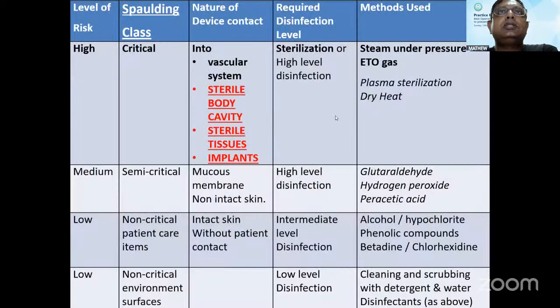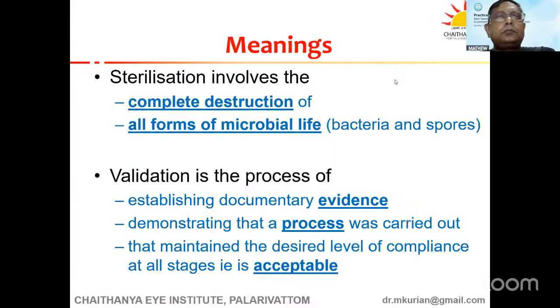Okay. Now, what is the level of sterilization? This is on the basis of the Spaulding's classification. So anything that goes into a body cavity needs to have the benchmark high-level autoclaving, which is steam under pressure. ETO is also acceptable. Plasma sterilization and dry heat are alternatives in this. But for me, the benchmark has always remained autoclaving.